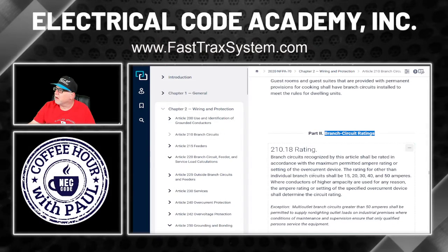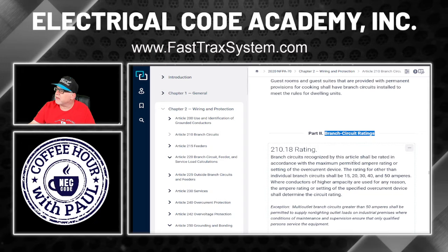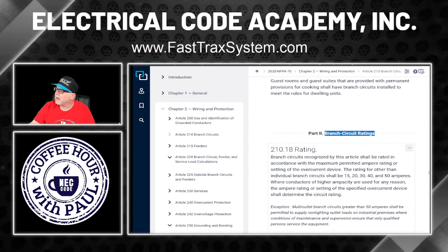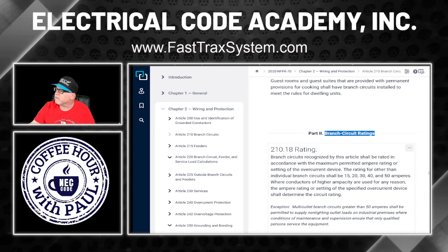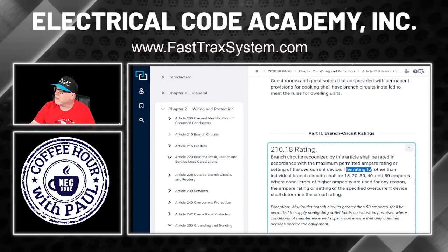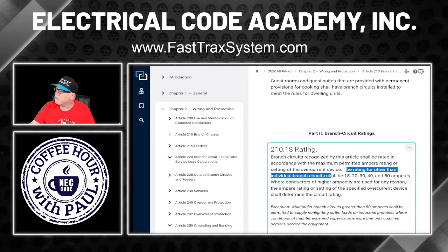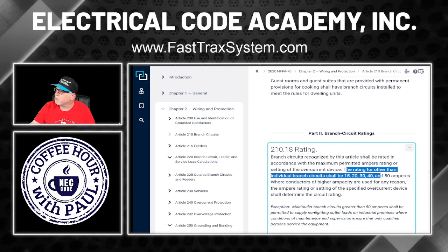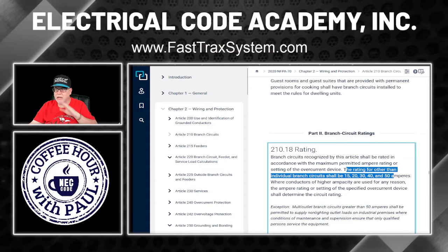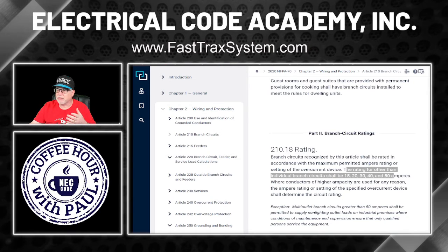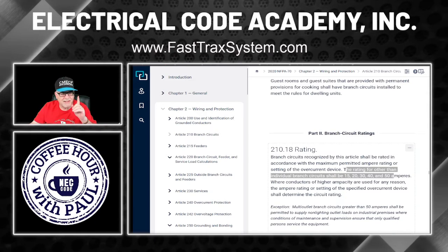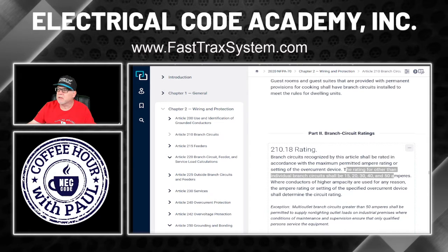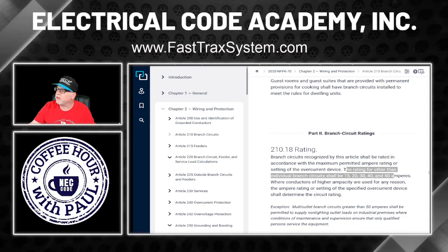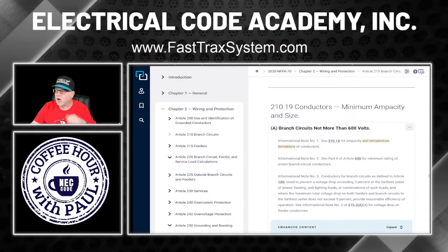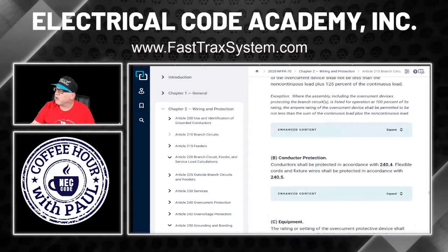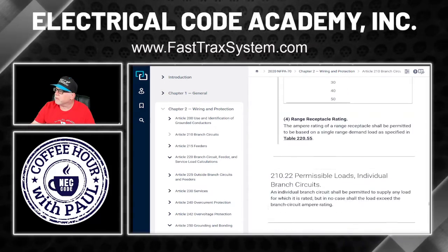Maximum rating. All right, so in the 18, it says, branch circuits recognized in the article shall have a rating in accordance with the maximum permitted ampere rating or setting of the overcurrent device. Okay? So the rating of the overcurrent, the rating other than individual shall be 15, 20, 30, 40, and 50. Okay, that type of thing. So it looks like we're going to pick 20 because that's the rating of the branch circuit, and cord and plug connected can't exceed that, but we're not stopping there because we saw permissible loads. Okay, so this is talking about the maximum rating, but we're going to finish this out unless you're just ready to click it and move on. But we want to go look real quick, and we're just going to jump to .22. Okay, permissible loads.